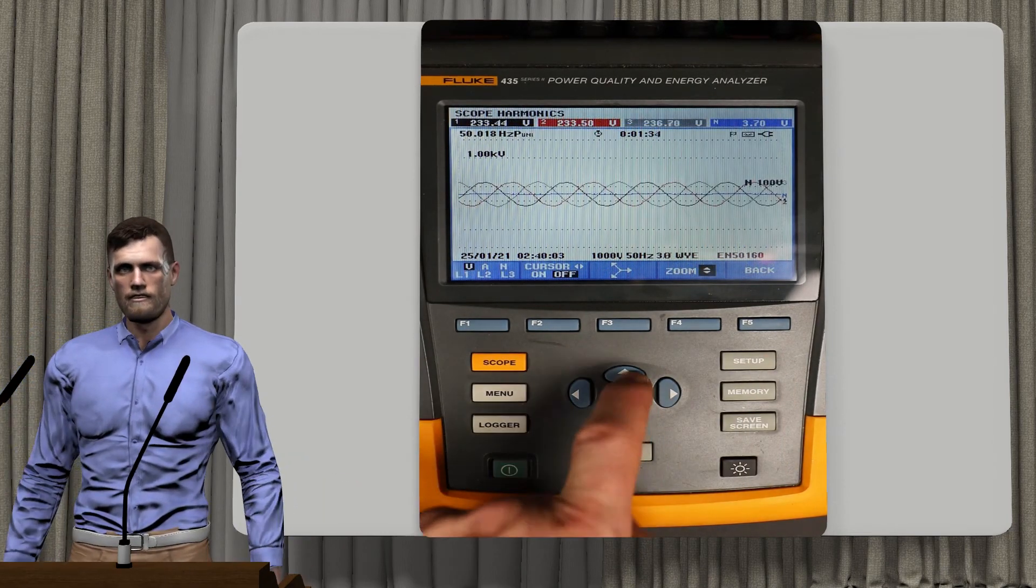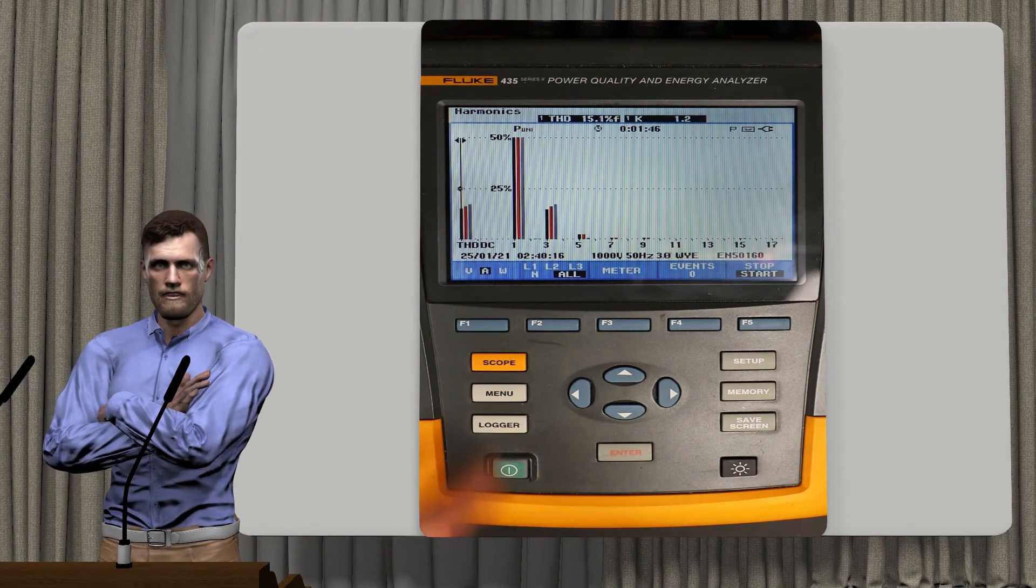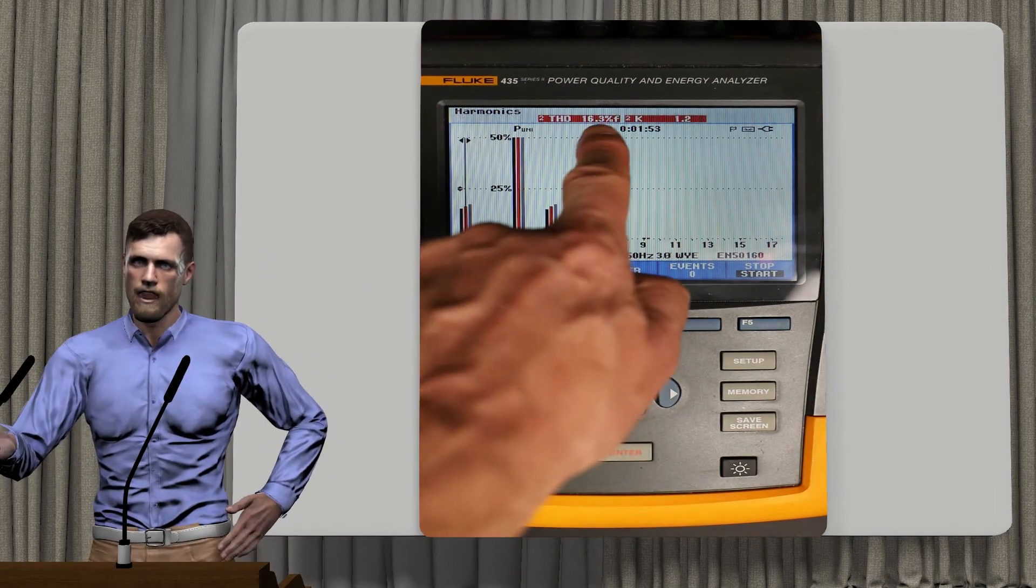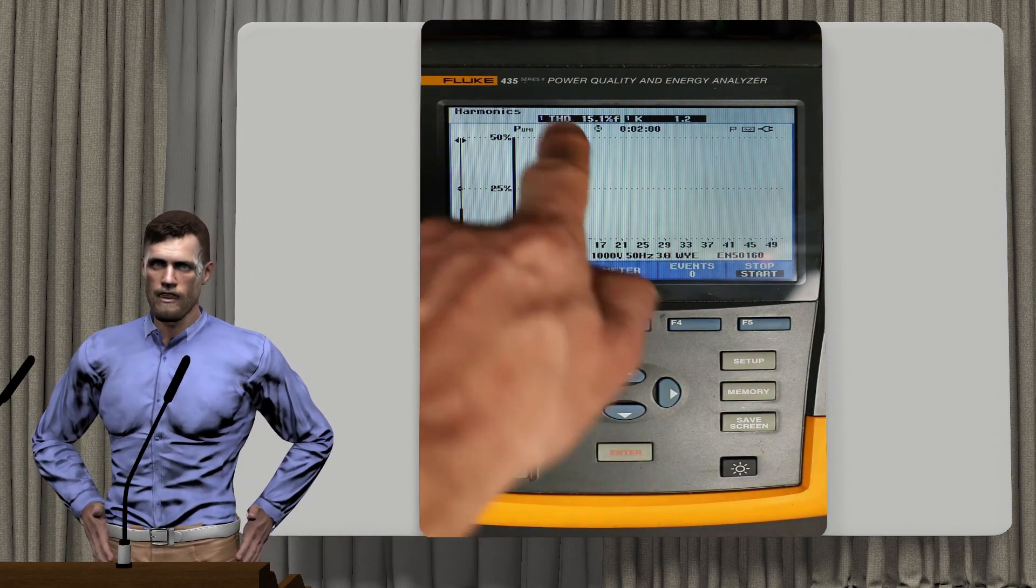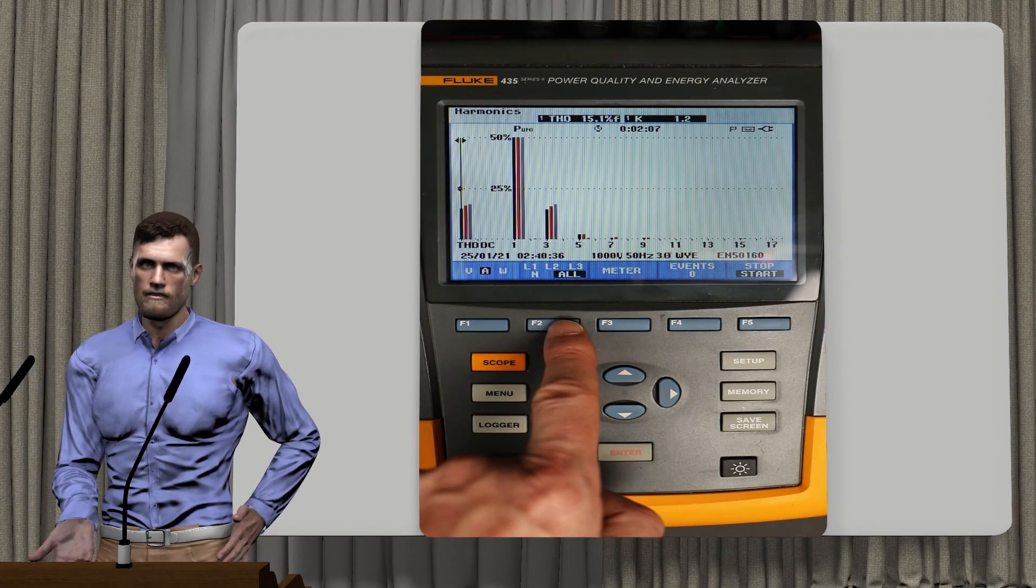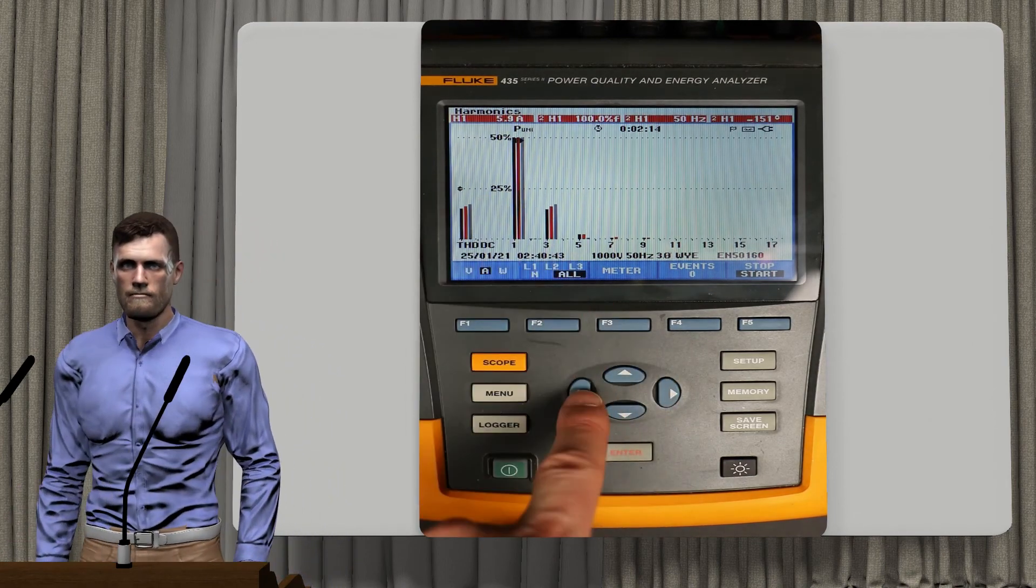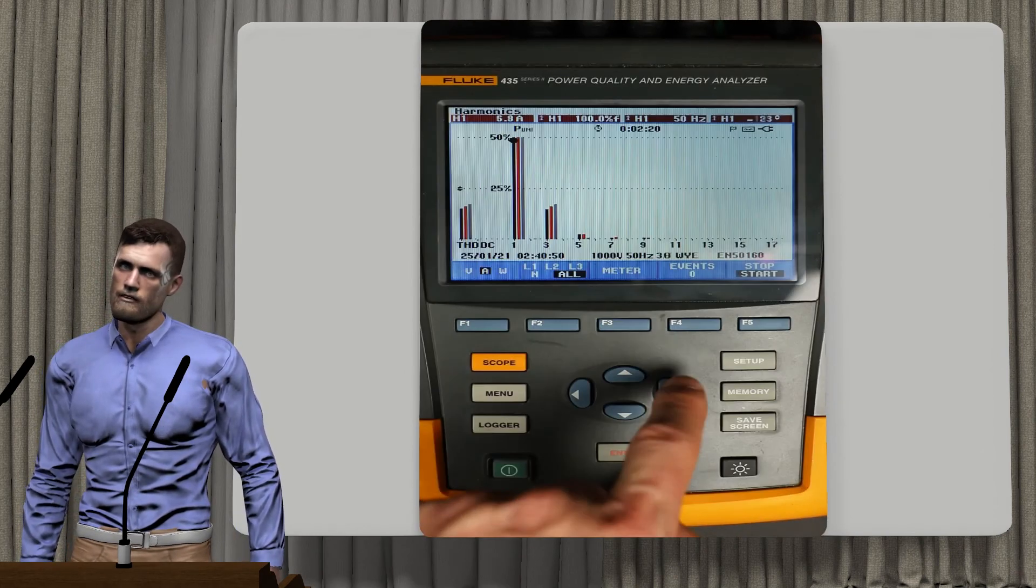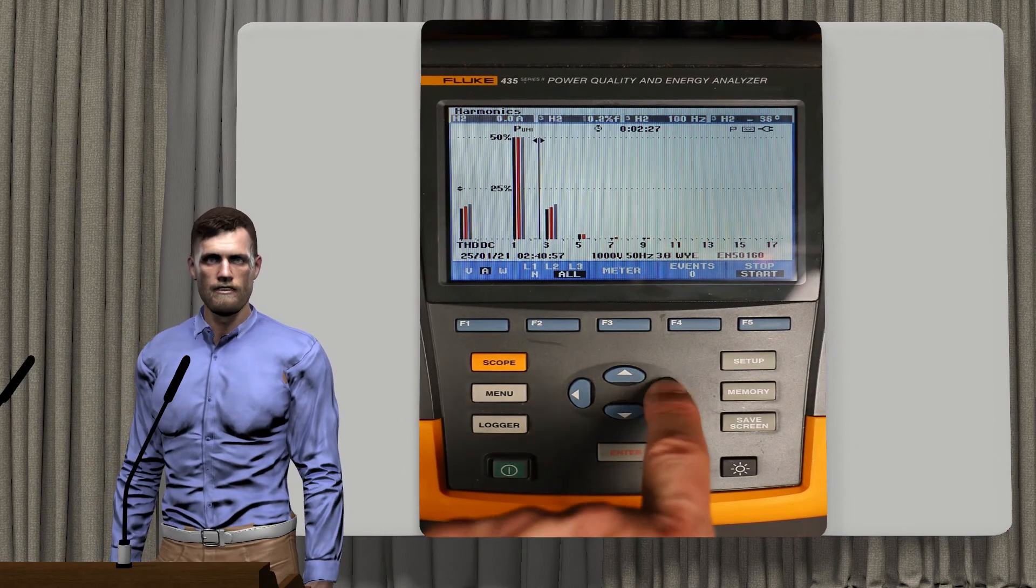We can also use the cursor to move over each of the bars, starting on the left with the THD of each phase. At the top of the screen, the measured numerical value associated with the parameter at that moment will appear. With the right and left arrows we can move the cursor. Likewise, to facilitate viewing, with F2 we can select a specific phase. In the case of moving the cursor to the fundamental component or any harmonic, in the upper part the value will appear in absolute magnitude, for example in amps or volts, also as a percentage value with respect to the fundamental component, the associated frequency and the associated phase shift.